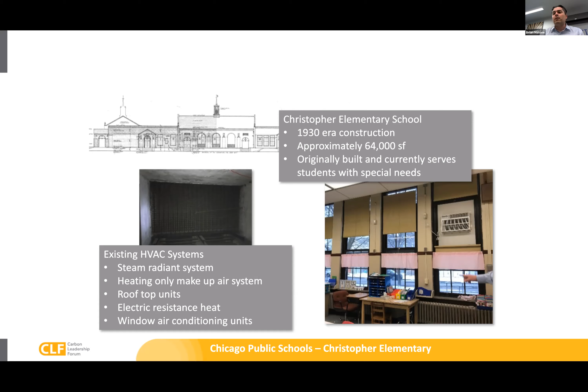However, we found that it wasn't entirely sufficient for a modern HVAC system. There had been various rooftop units installed over the course of several additions, and some of the newer additions from the 70s and 90s were installed with electric heat, so they didn't extend the steam boiler system to serve those portions of the building. They just installed electric resistance heating coils to serve those areas.